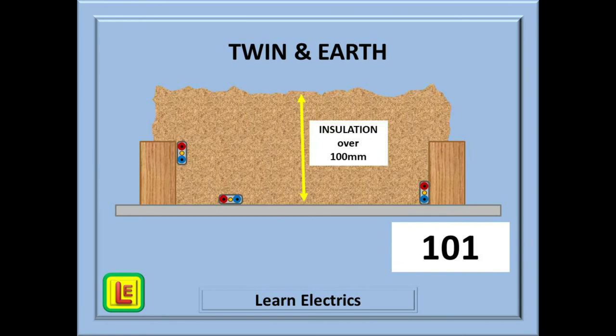If the insulation is over 100 millimeters in thickness, now we need a reference method with a number over 100. Well, 101 is over 100. And each cable is touching another surface, so our reference method for insulation over 100 millimeters is 101.